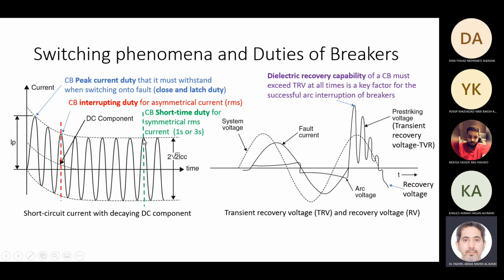Also in the breaker, they specify the short time duty, which means how long this breaker should wait closed while it is in a closed status during short circuit for the purpose of coordination. As long as there are faults, the breaker doesn't operate. You want the other primary breakers to operate, so it should wait. How long should this wait when there is a short circuit at this specified current?